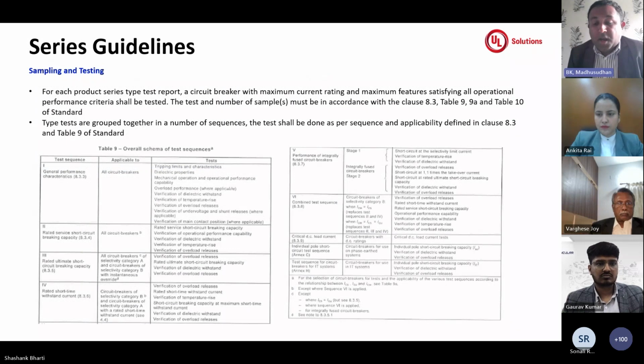Yeah. And coming back to the list of tests that is coming from the standard for this category. As per table 9, there is a list of tests that has been shared for meeting the construction requirements on these products. They are covered with respect to test sequences 1, 2, 3, 4, 5, and 6. Test sequence 1 speaks about general testing on the product. Basically it covers all the tripping characteristics, dielectric properties, temperature rise, operational performance on the product, followed by the post verifications of temperature rise and the dielectric.